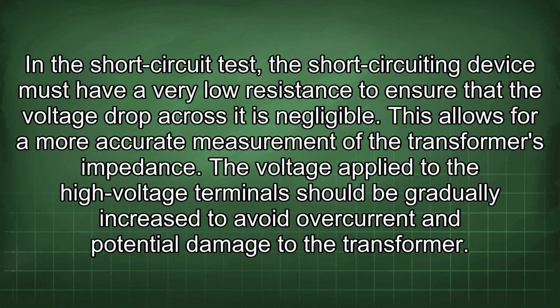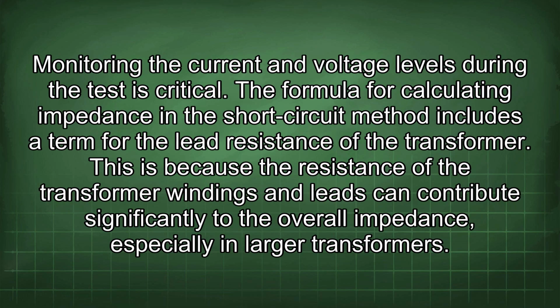In the short-circuit test, the short-circuiting device must have a very low resistance to ensure that the voltage drop across it is negligible. This allows for a more accurate measurement of the transformer's impedance. The voltage applied to the high-voltage terminals should be gradually increased to avoid overcurrent and potential damage to the transformer. Monitoring the current and voltage levels during the test is critical.